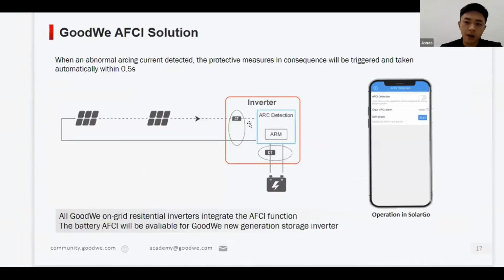So here, this picture shows how the GoodWe solution identifies arc faults and how it can prevent them. Based on the results of tests carried out on site, the GoodWe arc detection and protection solution adopts machine learning technology. As we know, if there is an arc, the characteristic curve of the current will be different from a normal current. Although it doesn't affect the power generation, it's a little different.